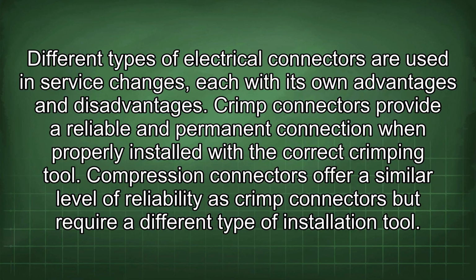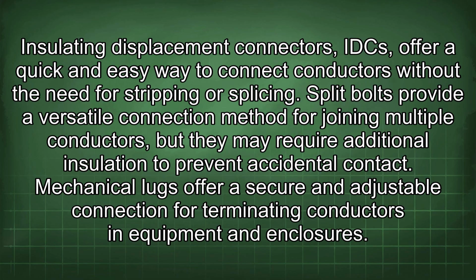Crimp connectors provide a reliable and permanent connection when properly installed with the correct crimping tool. Compression connectors offer a similar level of reliability as crimp connectors but require a different type of installation tool. Insulating displacement connectors (IDCs) offer a quick and easy way to connect conductors without the need for stripping or splicing. Split bolts provide a versatile connection method for joining multiple conductors, but they may require additional insulation to prevent accidental contact. Mechanical lugs offer a secure and adjustable connection for terminating conductors in equipment and enclosures.